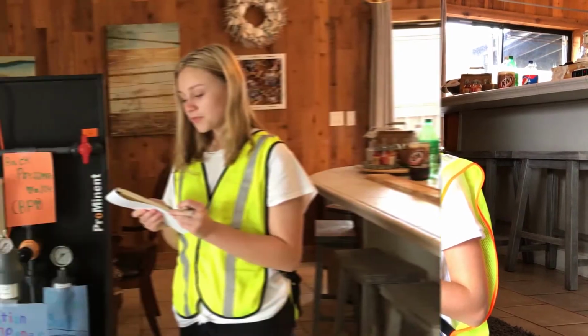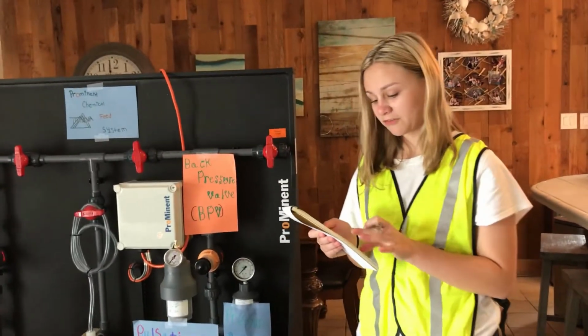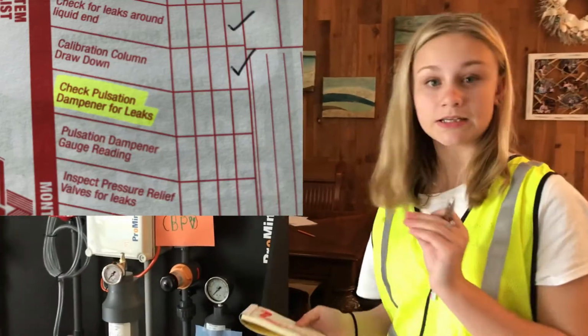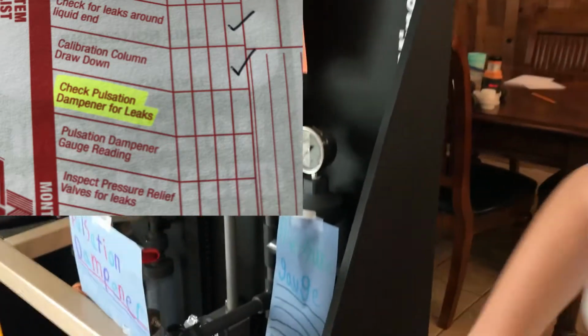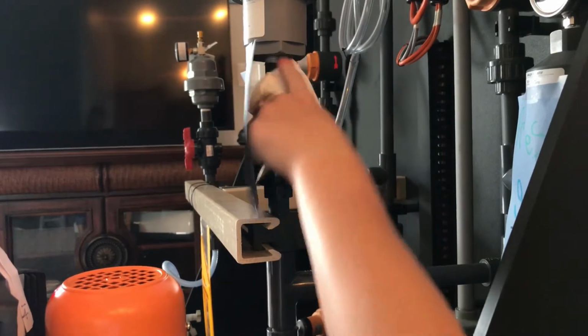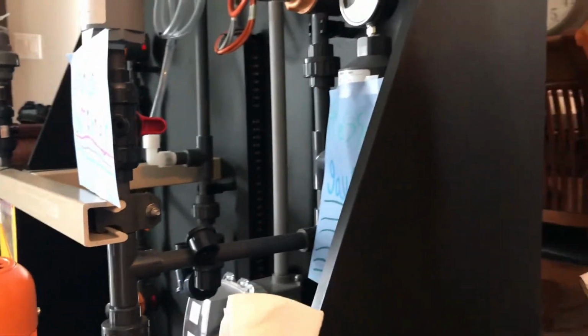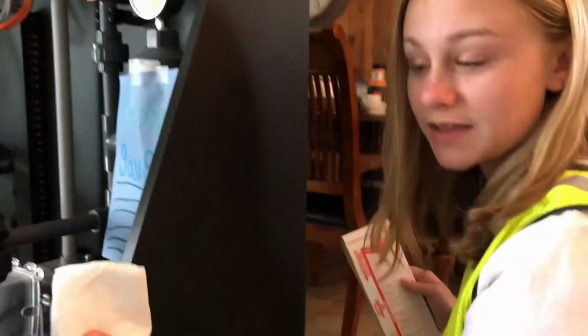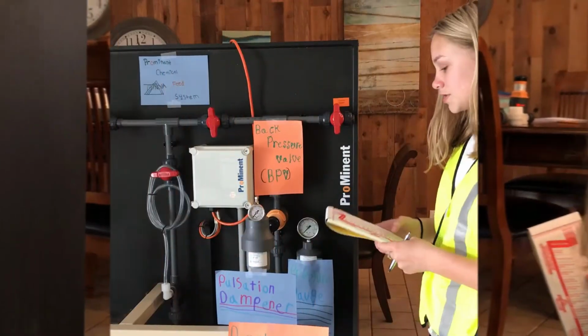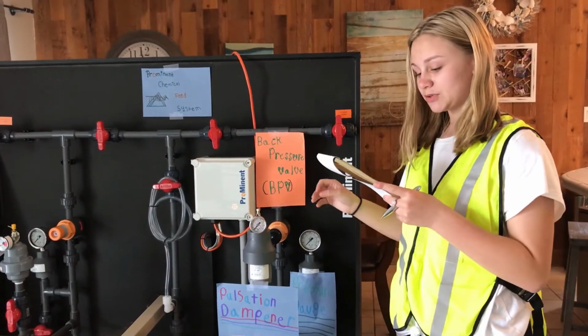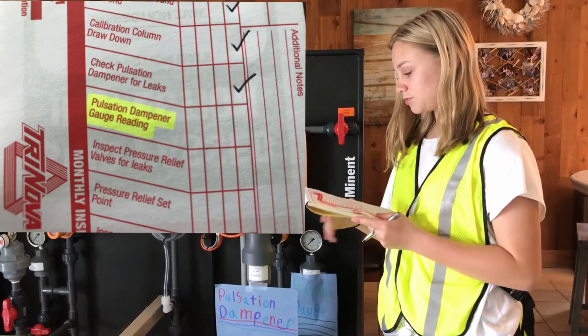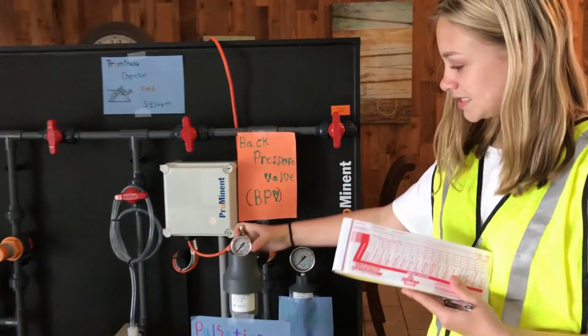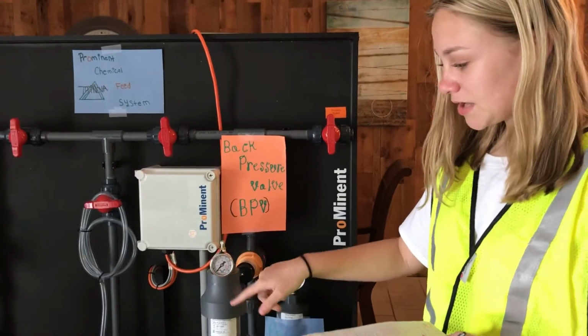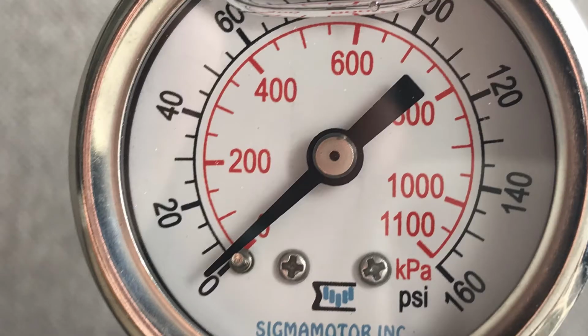The fifth thing that we're going to do is check for pulsation dampener leaks. You're going to take your paper towel or whatever you have, and you're going to see the threads. You're going to wipe it around here so there's no moisture or crystallization here. And that's how you check for your leaks. The sixth thing we're going to do is the pulsation gauge reader. So you're going to check it. If it's on 0, it ain't working.